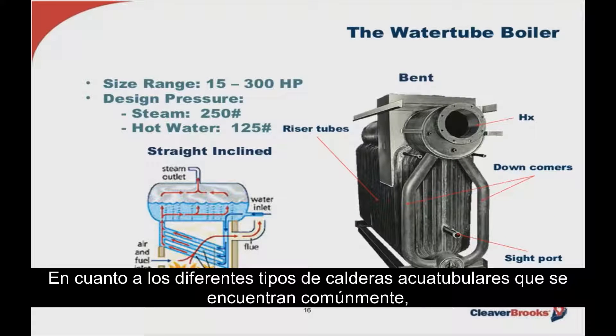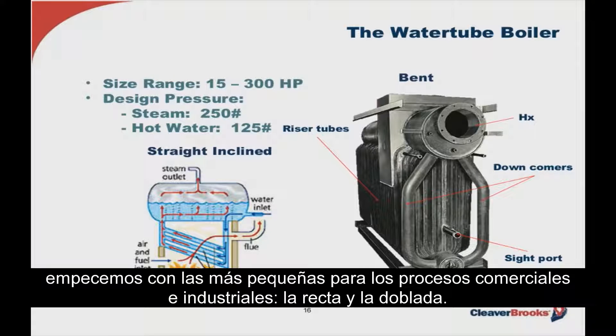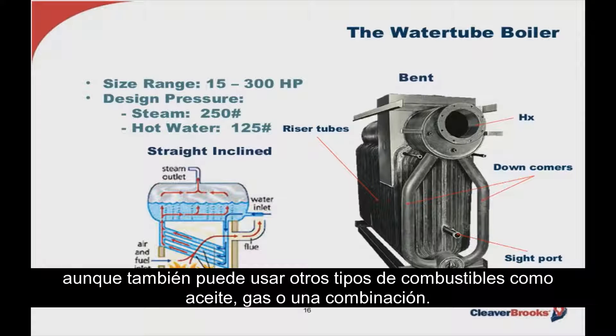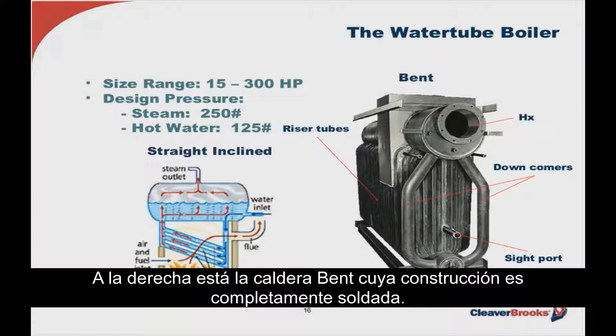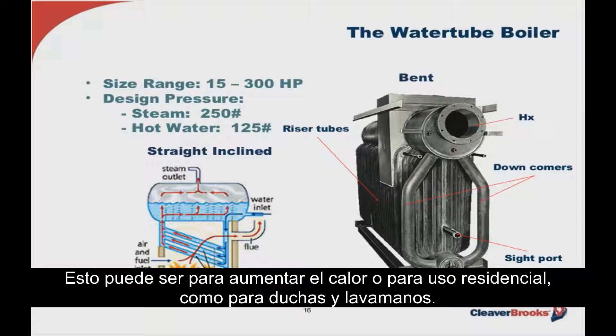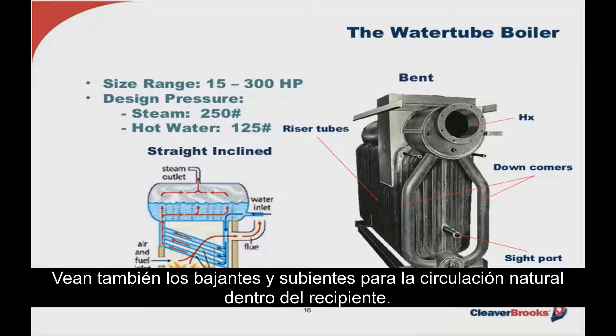Drilling down into the various types of water tubes, we start with smaller water tubes used in smaller commercial heating and industrial process applications: the straight inclined and the bent steel water tubes. The straight incline type uses an atmospheric gas burner, but these can also be equipped with power burners burning oil, gas, or a combination. The bent water tube pressure vessel has all welded steel construction. It's also being used to heat hot water through a heat exchanger placed in the upper drum connection, possibly for building heat or domestic use such as sinks or showers.